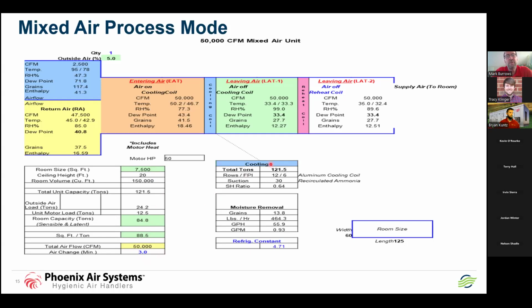Very, very safe configuration. Typical on these with a wet coil, so we don't frost the coil, is a 12-row, 6 fins per inch. This is important. A lot of commercial guys might look at this and say, let's get as much heat transfer as we can. You get the most bang for your buck on the secondary, which is the fin stock. We never, ever would like to go tighter than 6 fins per inch. Number one, those are going to be really thin fins. We like to use a 0.014, which is a pretty stout fin, versus sometimes guys will use a 0.007.